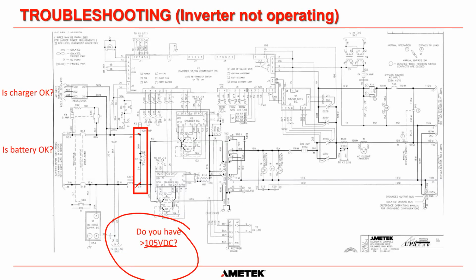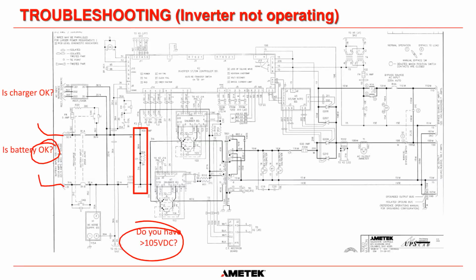You must have, for a 60 cell lead acid system, more than 105 volts DC, or the inverter will not start, because we take that DC and it goes into these pins here on the control board. And if we don't have 105 volts, the inverter will not start. So that's the first thing. So we need to check, is the battery okay? If you have less than 105 volts DC, has the battery been discharged? Is there something going on with the battery? Is there an external disconnect between the battery and the UPS system that may have been accidentally left open? That happens quite a lot.